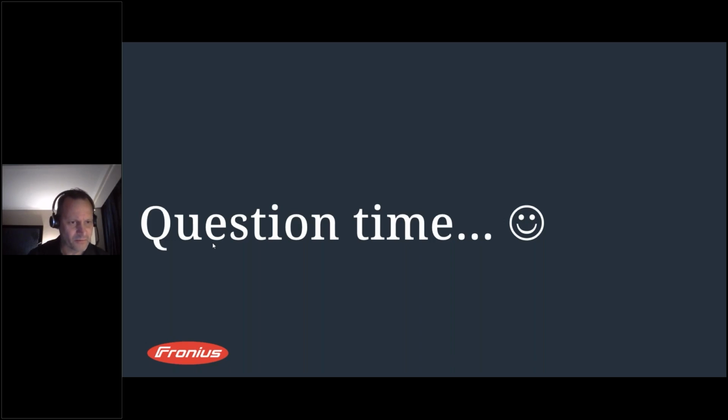Emergency backstop mode, the system production won't be, so it says here, won't be available for self-use as well, right? So this is the fun one with the DNSP. Look, it's still not 100% clear, but from what we've heard, the first command will be an export limit. Because it's an export limit, whatever the site consumption is, the inverter will still ramp itself up and down in order to offset that. We have heard some limits of 0 export, so it'll go to a 0 export, but still meaning you can offset your own loads for self-use.